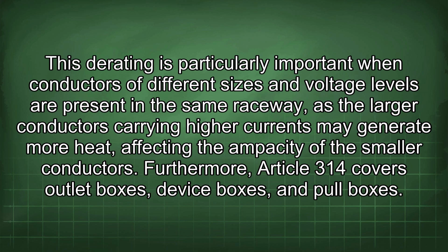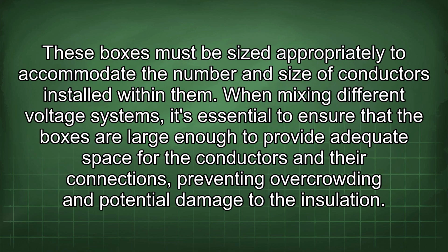Furthermore, Article 314 covers outlet boxes, device boxes, and pull boxes. These boxes must be sized appropriately to accommodate the number and size of conductors installed within them. When mixing different voltage systems, it's essential to ensure that the boxes are large enough to provide adequate space for the conductors and their connections, preventing overcrowding and potential damage to the insulation.